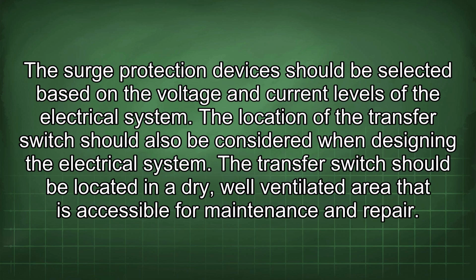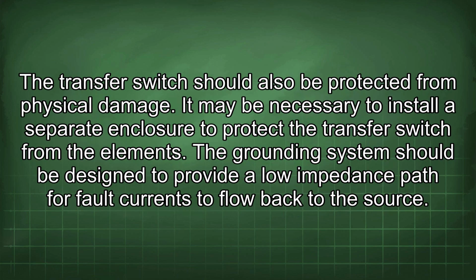The location of the transfer switch should also be considered when designing the electrical system. The transfer switch should be located in a dry, well-ventilated area that is accessible for maintenance and repair. The transfer switch should also be protected from physical damage. It may be necessary to install a separate enclosure to protect the transfer switch from the elements.